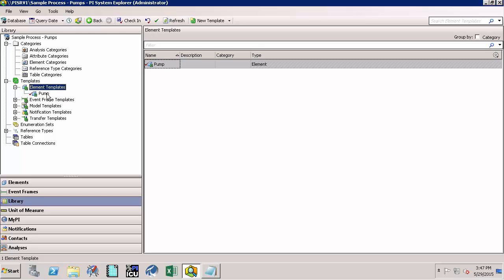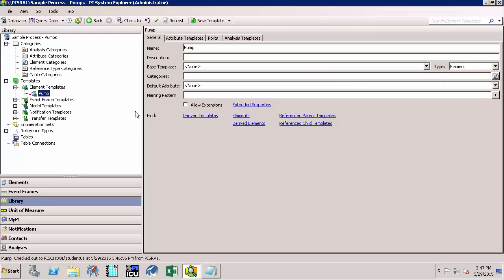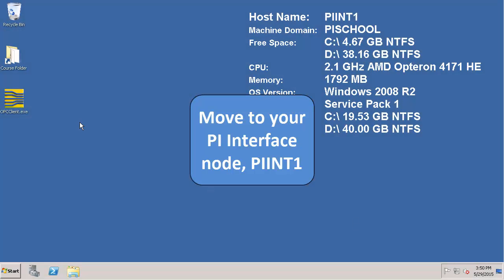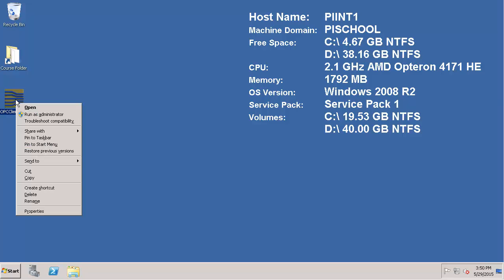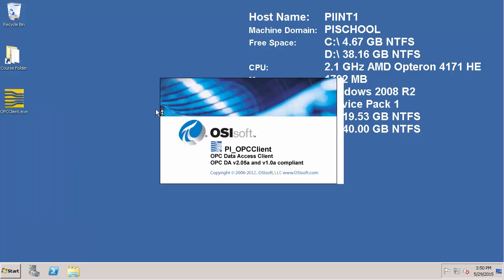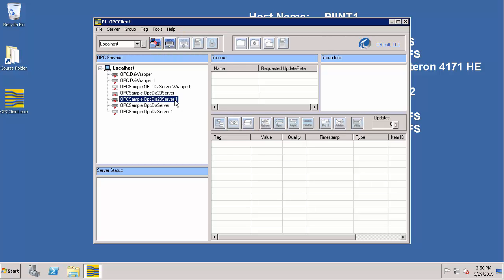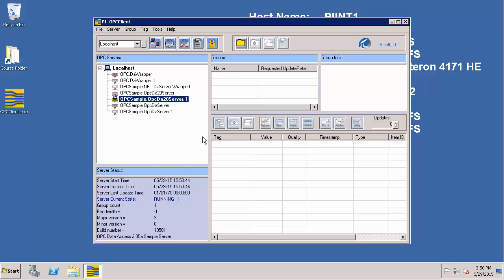Now expand Element Templates and click on Pump. Let's define a few attributes for the pump to correspond to the names on the OPC server. To see that, let's first minimize PI System Explorer and go to the PI Int1 machine. Once we are on PI Int1, from the desktop right-click the OPC client executable and select Run as Administrator. Now let's connect to the node which contains the OPC server — it's localhost. Click on this button to connect to the node, then double-click on the OPC server we are interested in.